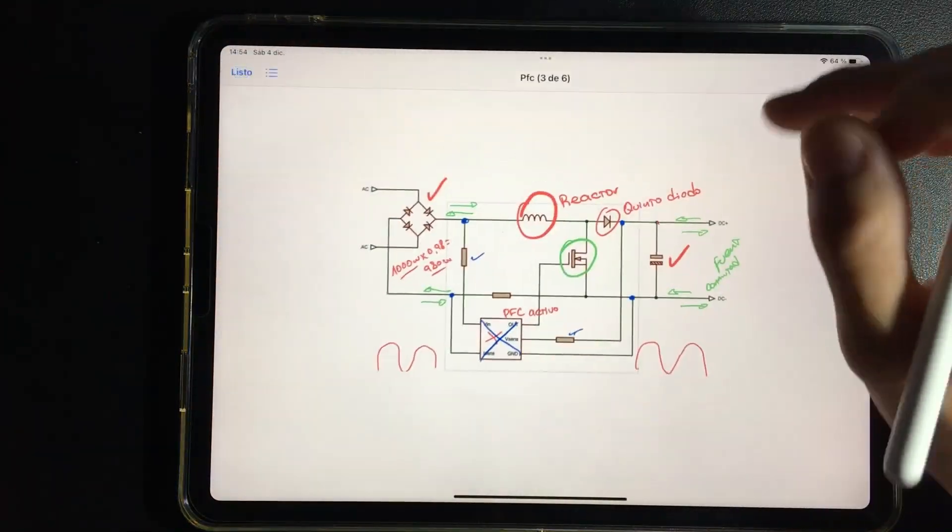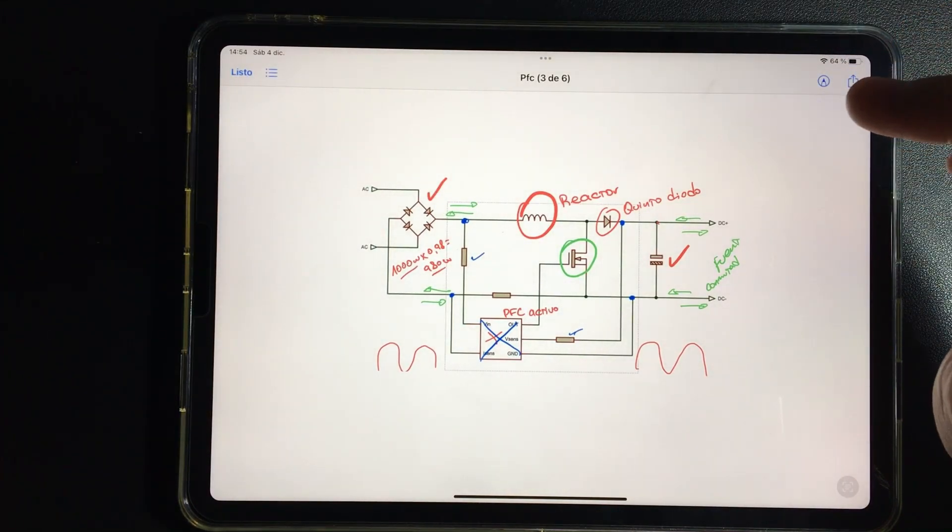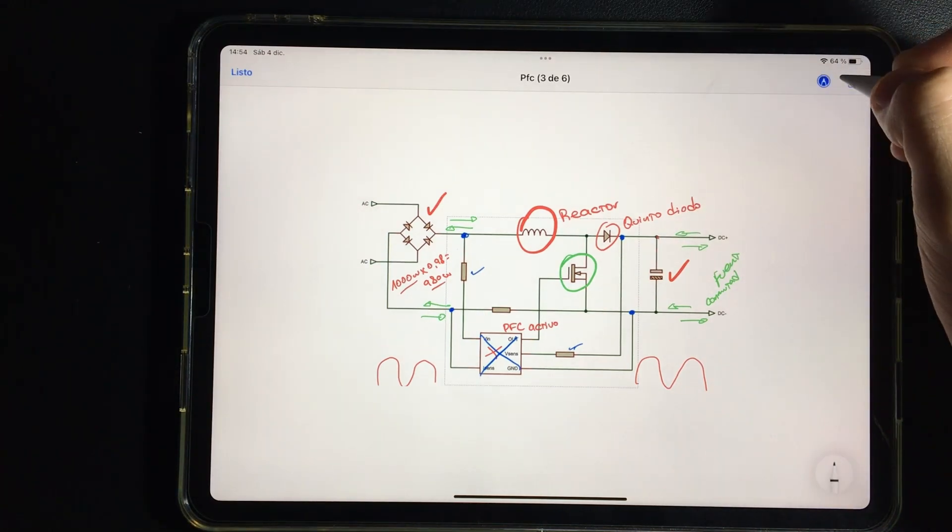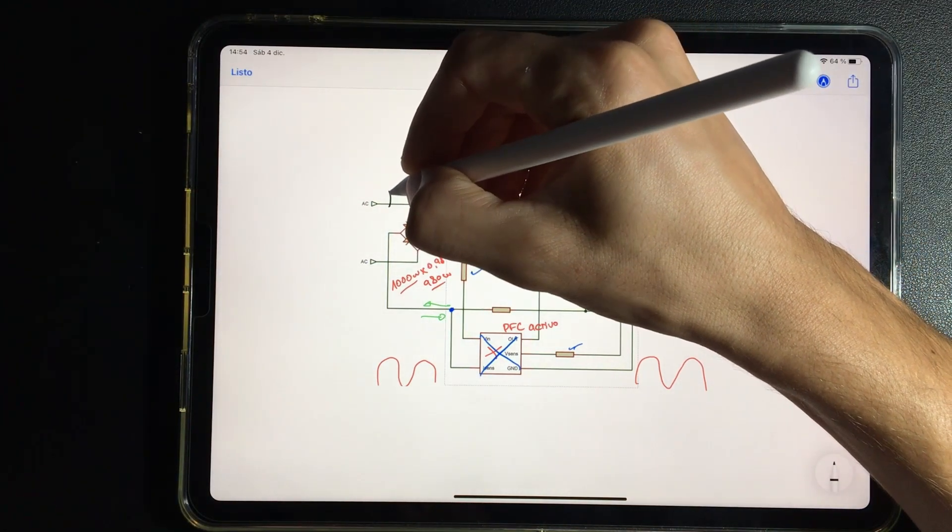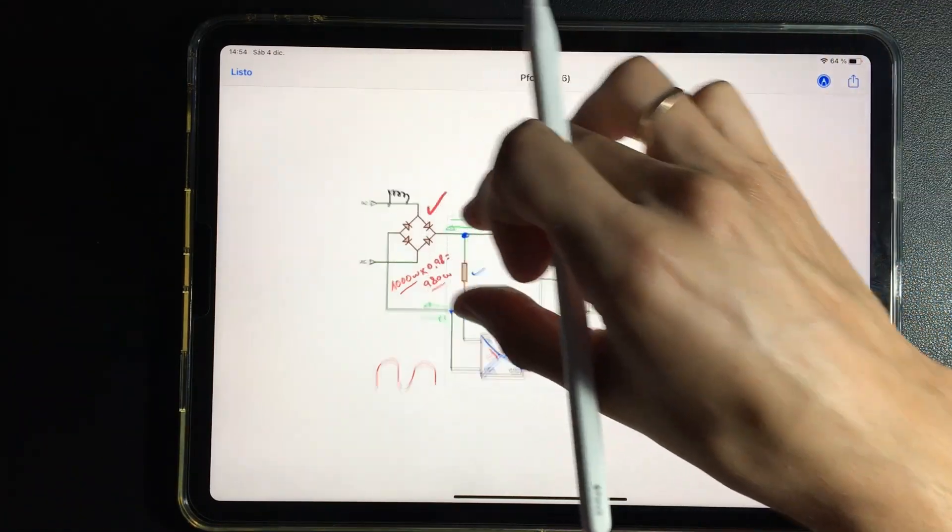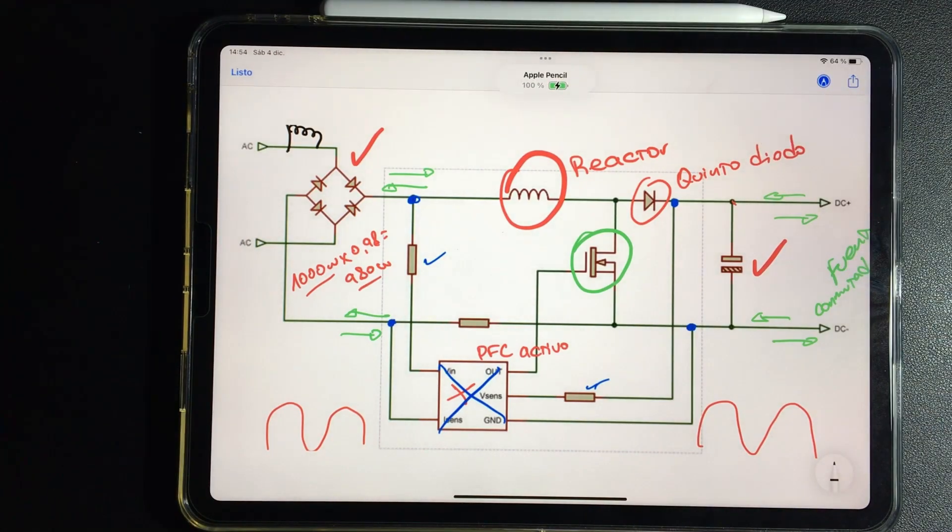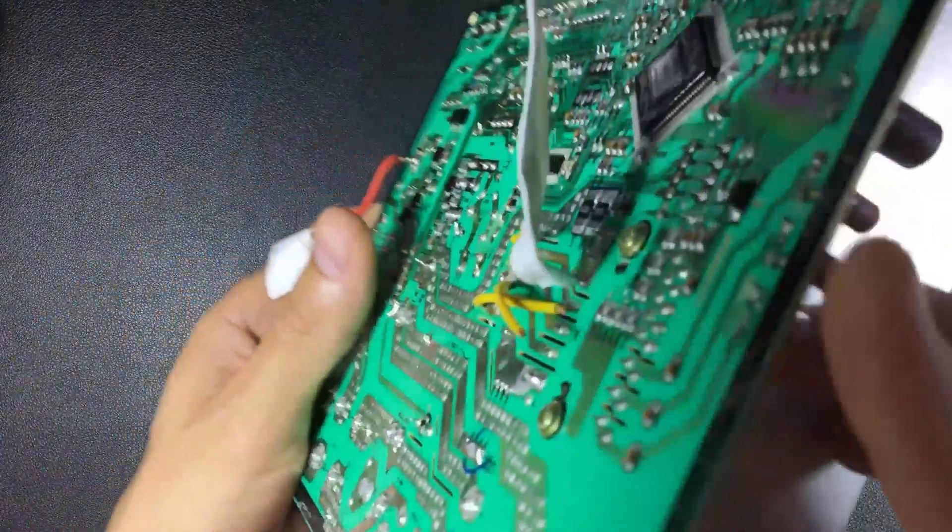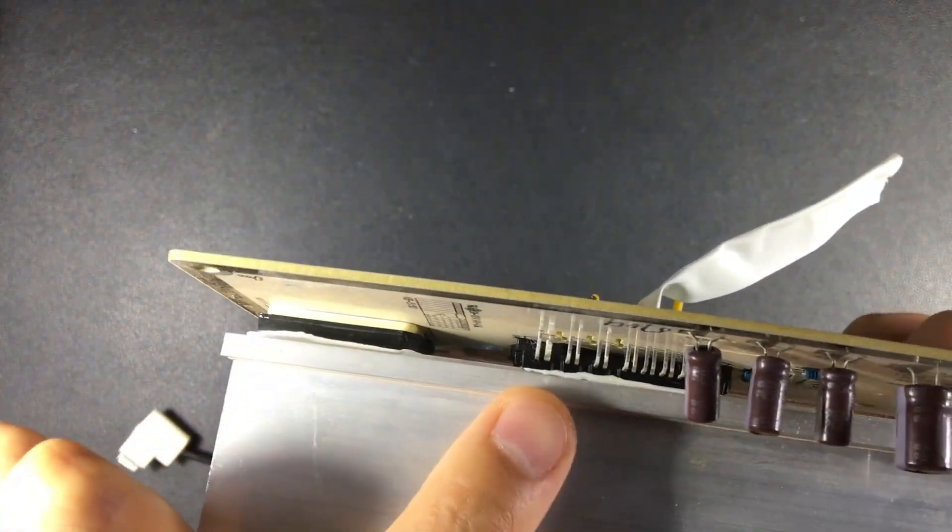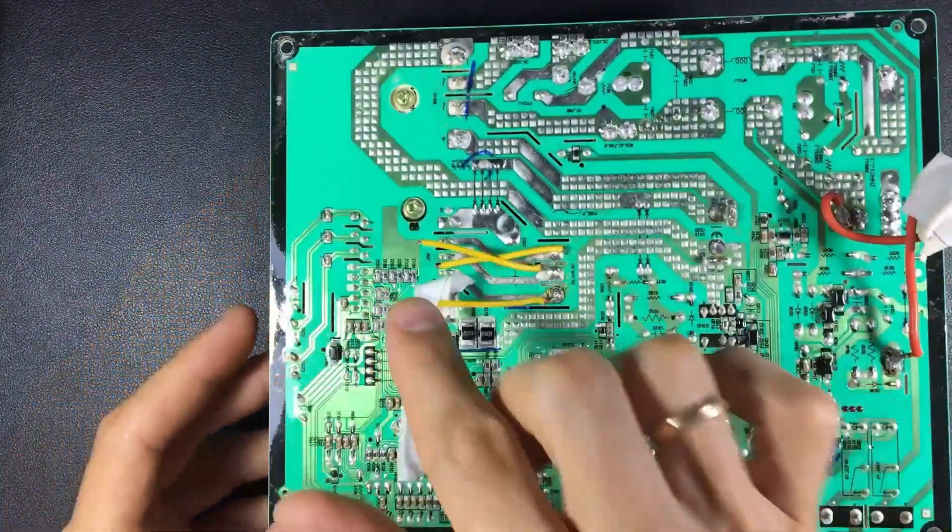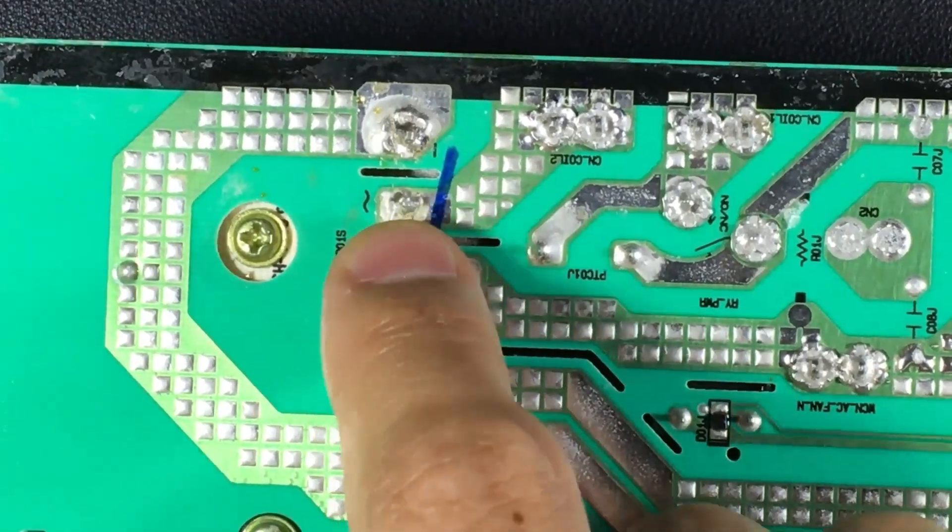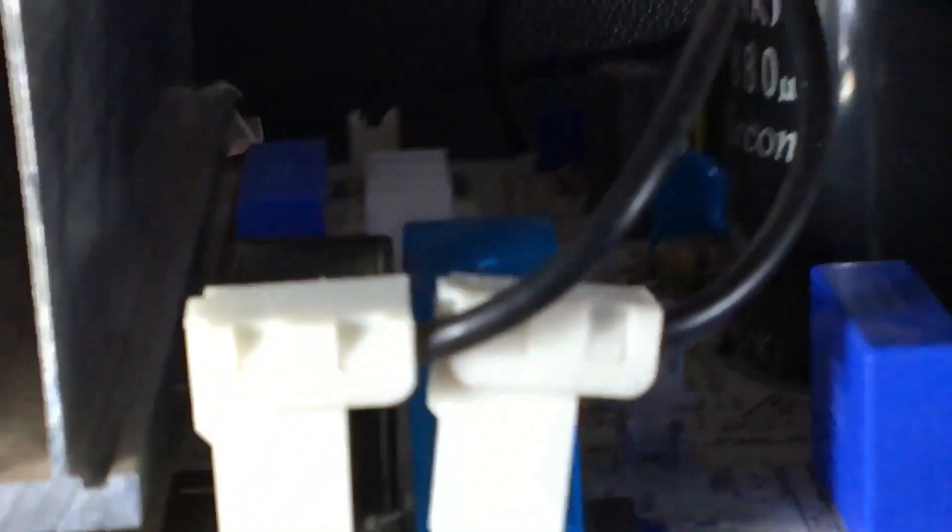One last detail, on certain electronic boards such as LG there is no active PFC. As there is no active PFC they place a reactor to correct power factor a bit and place it here. On alternating current at input, keep in mind that detail if you don't see active PFC. For example, on this LG board I'm going to show you now. If you don't see the active PFC, it's not there because there is only a rectifier and IPM. In this case, they place it on alternating current, there is where they place reactor. Here's where reactor is plugged in.